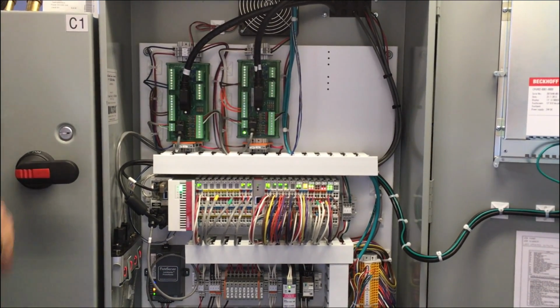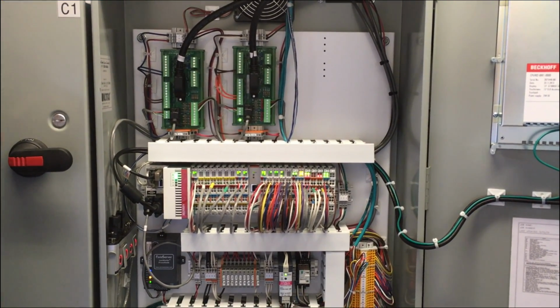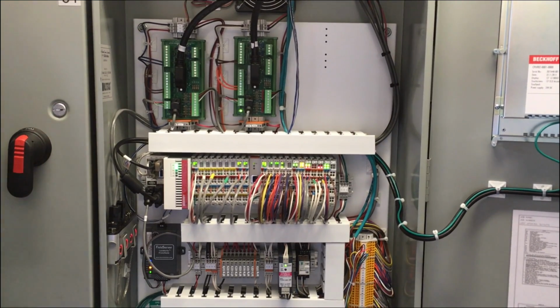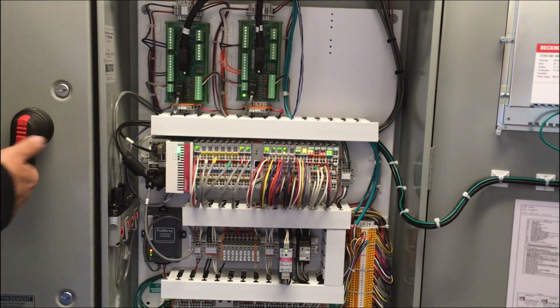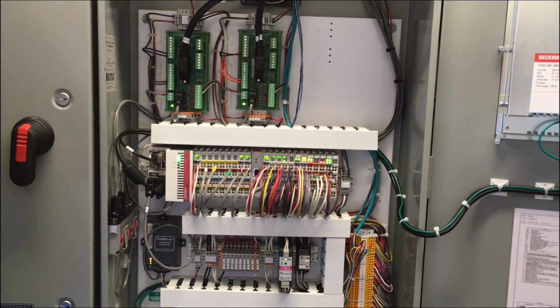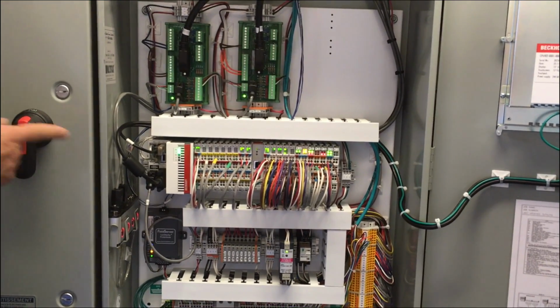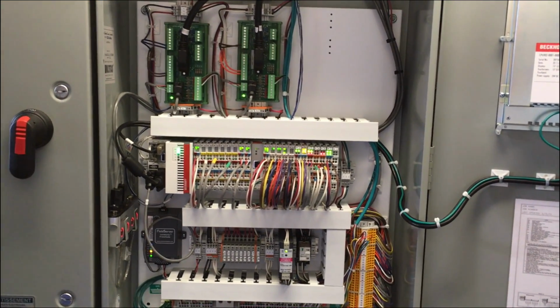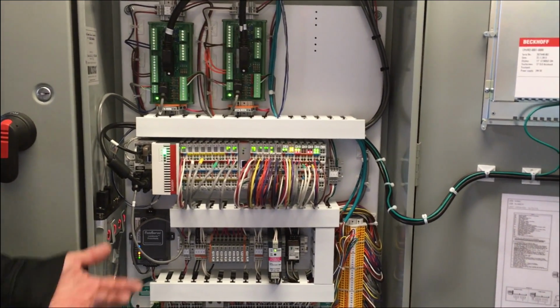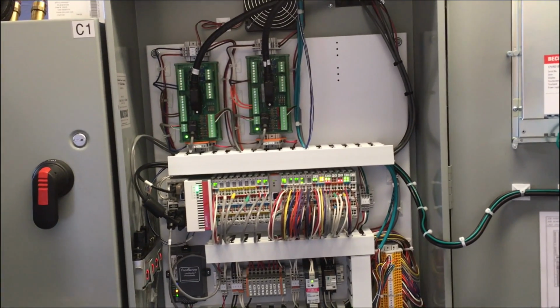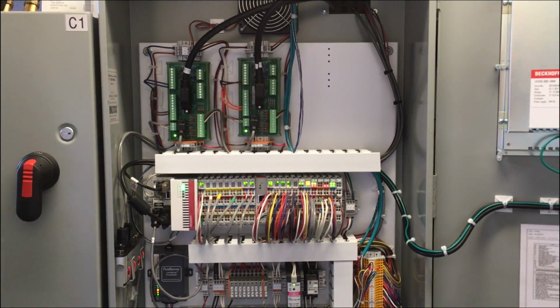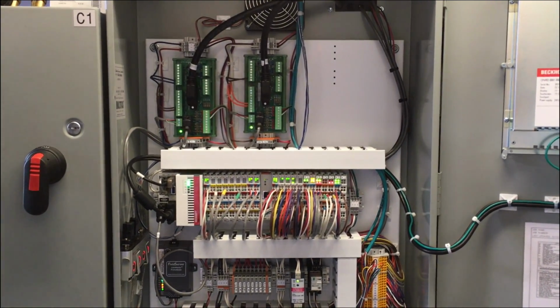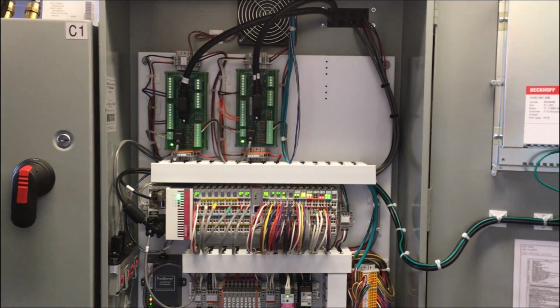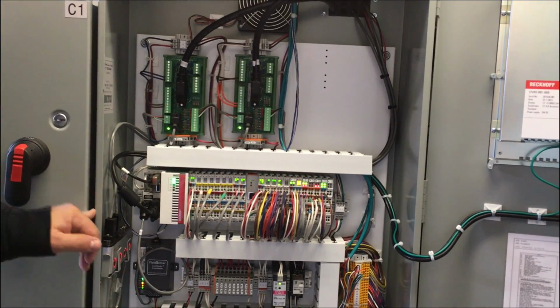So now that that's out, that resets all the hard lockouts on the compressor. And we can then turn it back on. If you turn it back on while that light's still green, compressor will start up again if it's not locked out, but if it had a lockout, it's not going to clear it. So that way, if you ever have a power failure, not every power failure is a minute and a half. Most of them are a second. Enough to take the compressor down and get it to reboot.